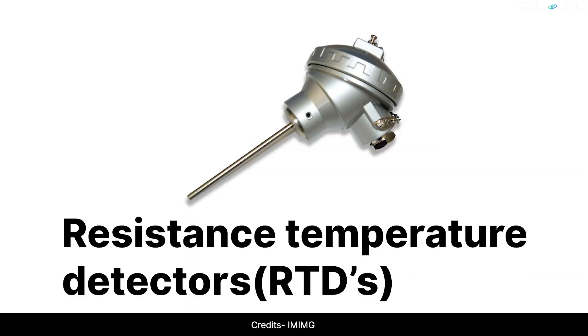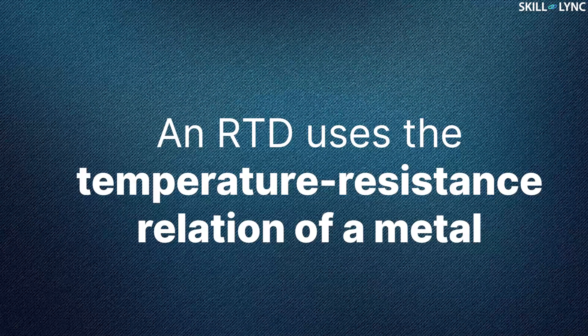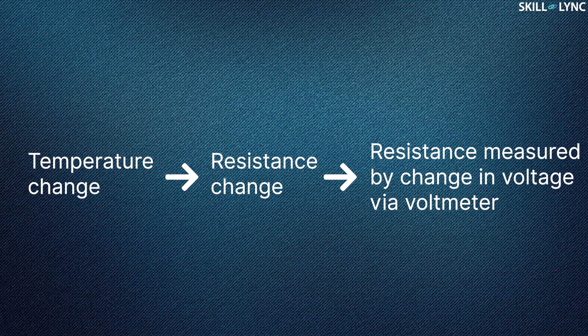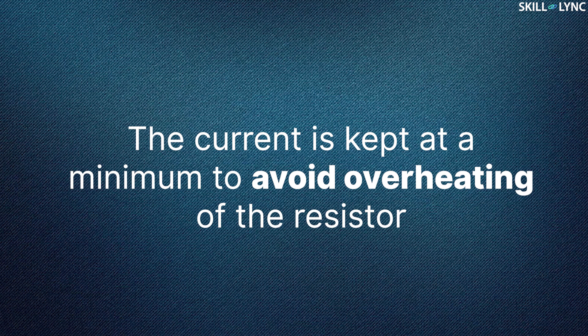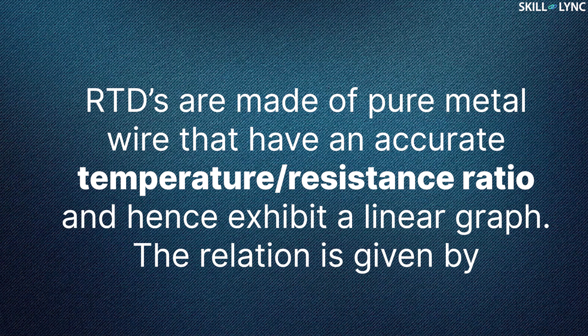Next, we have resistance temperature detectors or RTDs. An RTD uses the temperature-resistance relation of a metal. In practice, a constant current is passed through an RTD. As the temperature of the metal changes, the resistance of the metal also changes. This creates a change in the voltage across the sensor which can be measured via a voltmeter. The voltage indicates the change in temperature and thus the temperature change is measured. The current flowing across the sensor is kept at a minimum to avoid overheating of the resistor. RTDs are made of pure metal wire that have an accurate temperature-resistance ratio and hence exhibit a linear graph.